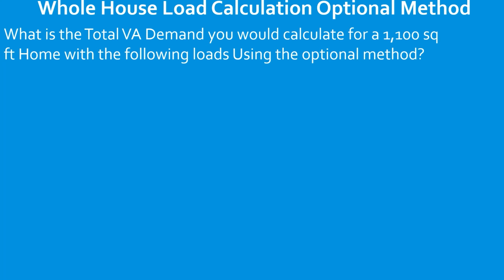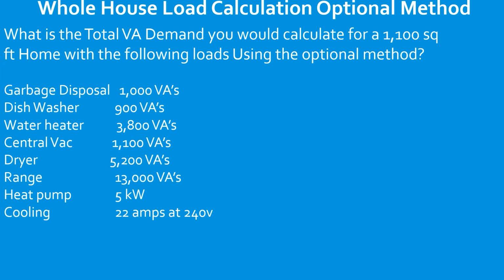What is the total VA demand you would calculate for an 1,100 square foot home with the following loads using the optional method? Okay, so we have all of our loads here: heating and cooling, range, dryer, and so on and so forth.